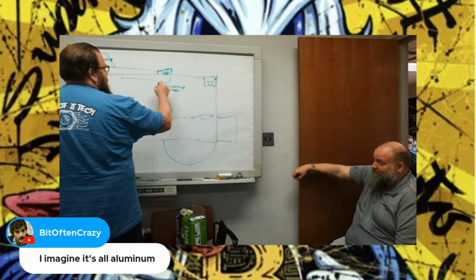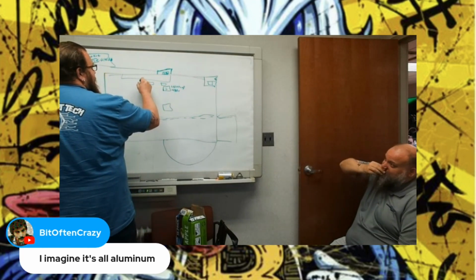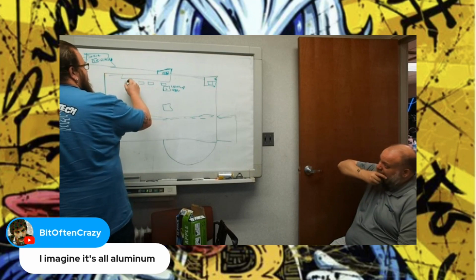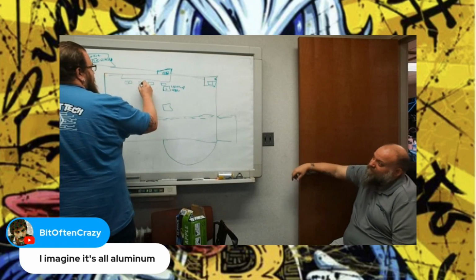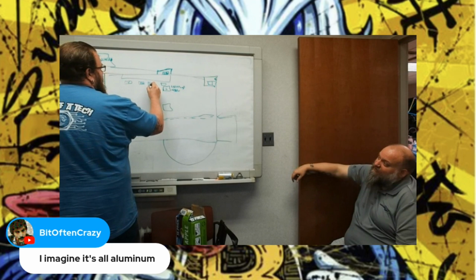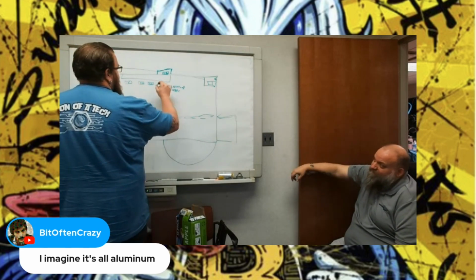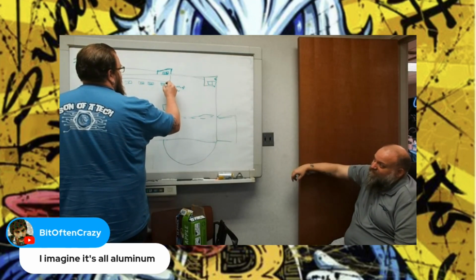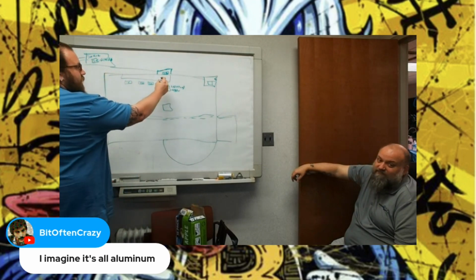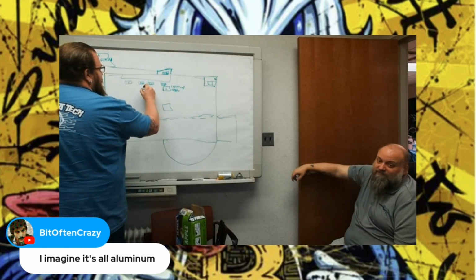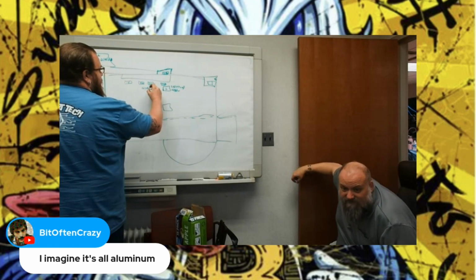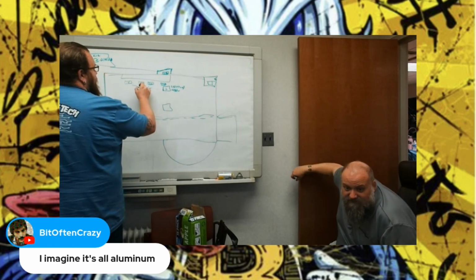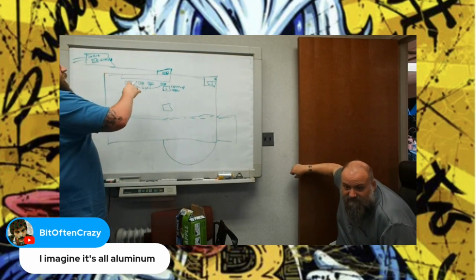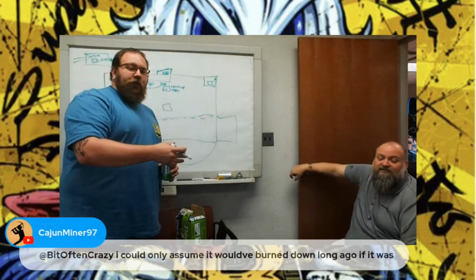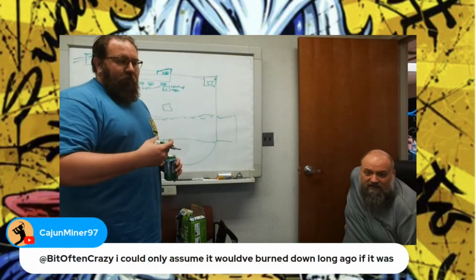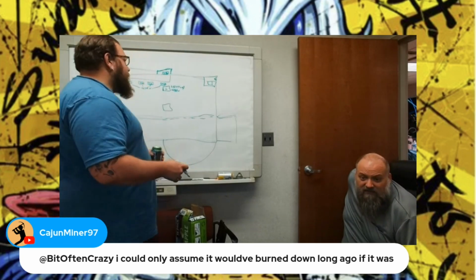So we have a 750, a 500, a 500, and a 1,000 kVA transformer. The 1,000 is in the future, and 750. So that's 480 to 415. These are all 415. 415 volts. Boom, boom, boom. So when we take that 415 down to the PDU level, that now becomes 240, which is what the machines run on. He's not wrong.